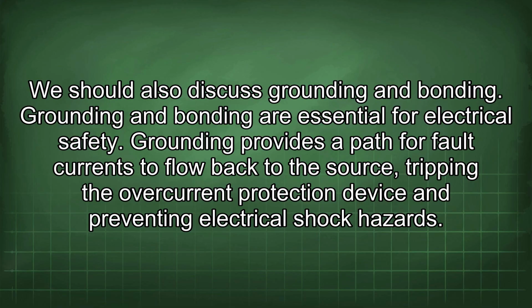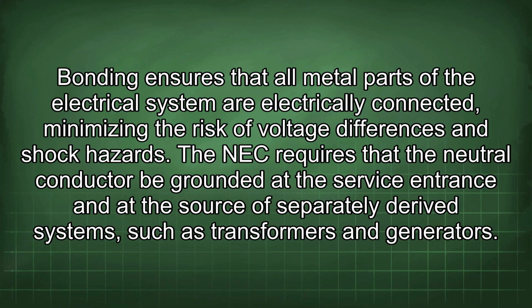Grounding and bonding are essential for electrical safety. Grounding provides a path for fault currents to flow back to the source, tripping the overcurrent protection device and preventing electrical shock hazards. Bonding ensures that all metal parts of the electrical system are electrically connected, minimizing the risk of voltage differences and shock hazards. The NEC requires that the neutral conductor be grounded at the service entrance and at the source of separately derived systems such as transformers and generators.